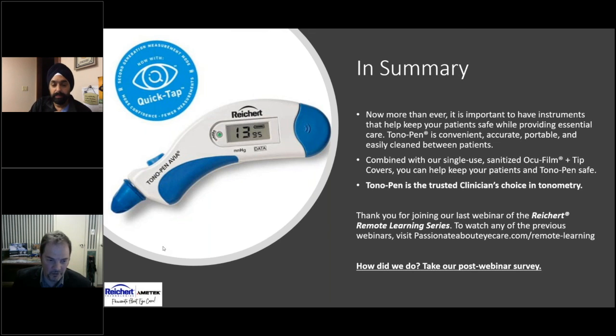Yeah, you touched on a few really important points there, especially when you said older technology. Whenever a customer calls our office or visits us at the trade show booth and says, my tonometer X is inaccurate, what's the cause? I always say, well, it's time to put our detective hat on and drill down into what's going on, because there are so many variables that can affect the accuracy and repeatability of all of these instruments. As you mentioned, an older air puff tonometer, even the ones that we manufactured 10 to 12 years ago, aren't anywhere near as accurate as the Ocular Response Analyzer and the 7CR that we produce today, because of the advancements we've made in measuring things like biomechanics and increasing the repeatability of those.